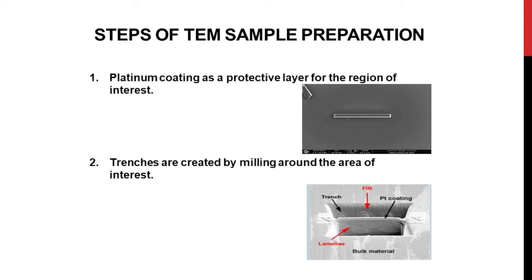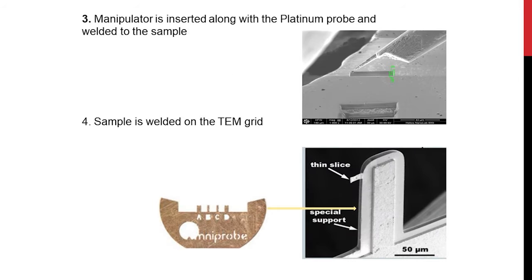Once the platinum is deposited, we create trenches around this deposition area, which is actually termed as milling — this is also called a cross section. The next step involves the in-situ manipulator, which aids you in sample preparation. We get the probe very close to the sample where the cut has been made — this process is termed lift-off. We weld the sample lamella to the probe with the help of platinum, lift off the lamella, and finally attach it to the TEM grid. This is called a half moon grid which has different slots in it.